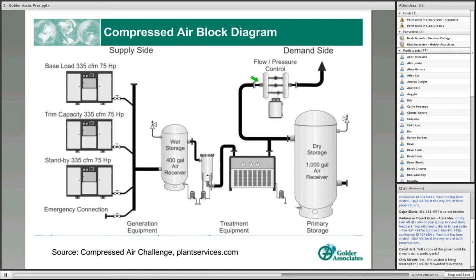Excuse me, in line with what Herb had discussed. So first look at the load side and see if you can eliminate some of the loads, and then once you have established the load, you should be able to do some savings, particularly if the compressors do not have, how should I say, a modern or a more sophisticated control system that speaks to all 4, or in this case, all 3 compressors.